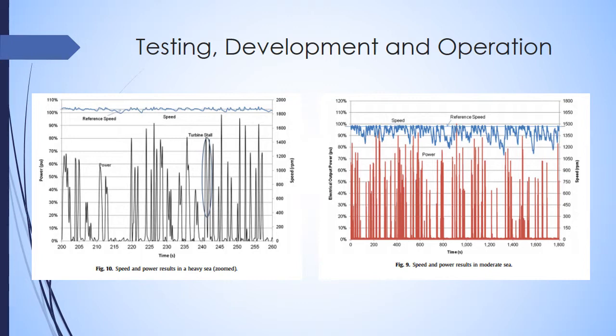Power is not supplied to the system to compensate for friction and windage losses in the system. Power is not drawn from the battery bank to maintain the speed. This creates dips in the plot as shown.